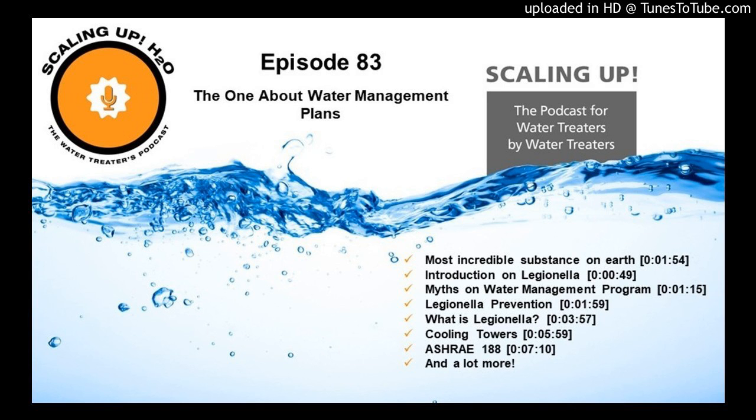You don't need to look at all the points of use, but you need to identify the key points: where it taps in at the street, where it enters the building, where the water heaters are, and some basic information about the water heaters, the type, the size, the number of them, and whether there are redundant ones in a given system. And any key components like central filters, not too many buildings have those, like a filter for the incoming water. But if they do, you would need to identify those, and softeners. So that's just the plumbing system.